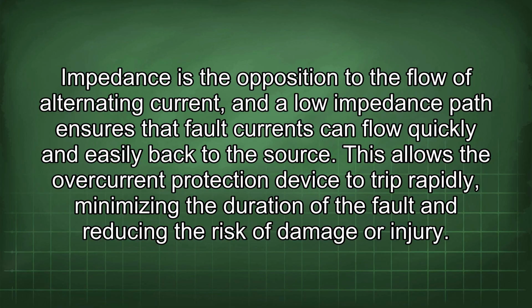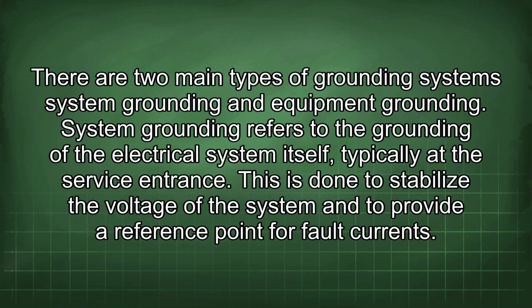This allows the overcurrent protection device to trip rapidly, minimizing the duration of the fault and reducing the risk of damage or injury. There are two main types of grounding systems: system grounding and equipment grounding. System grounding refers to the grounding of the electrical system itself, typically at the service entrance. This is done to stabilize the voltage of the system and to provide a reference point for fault currents.